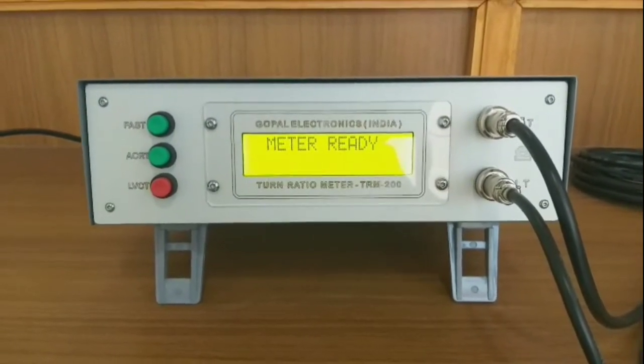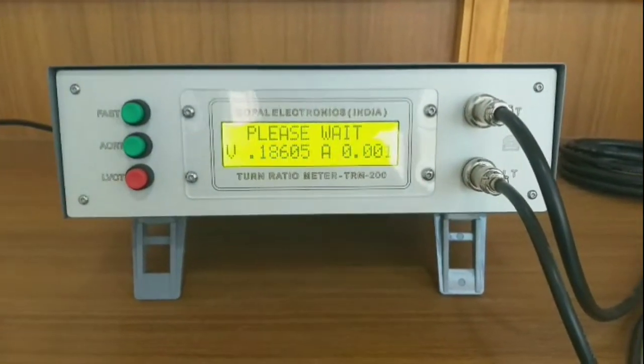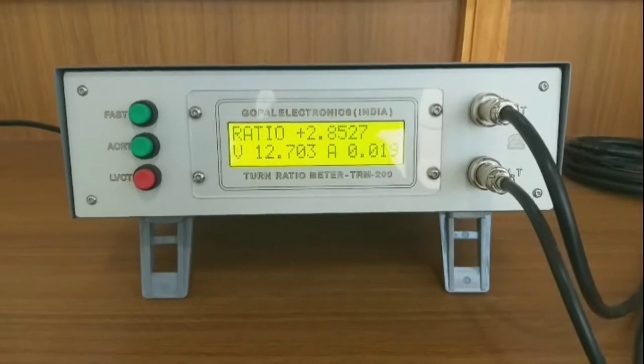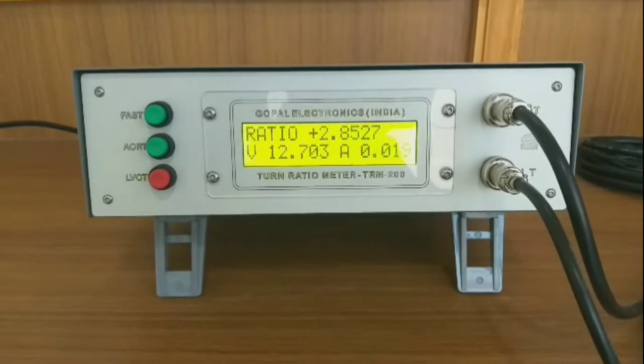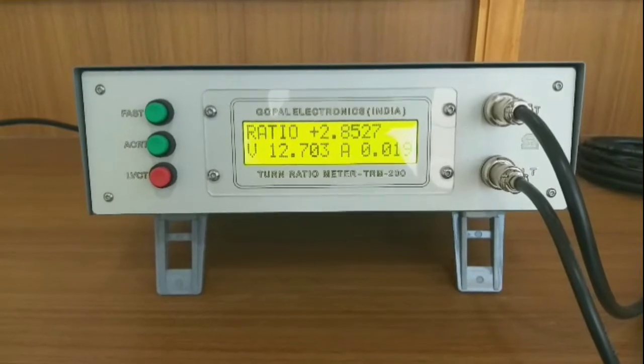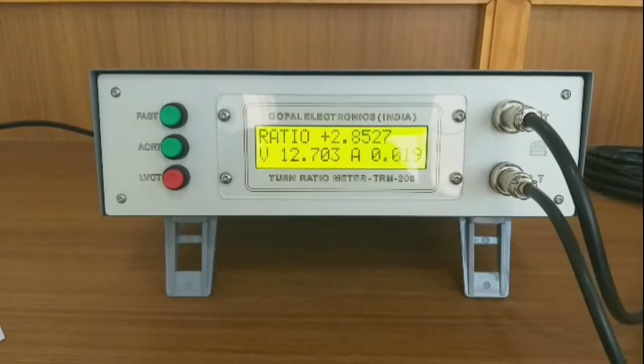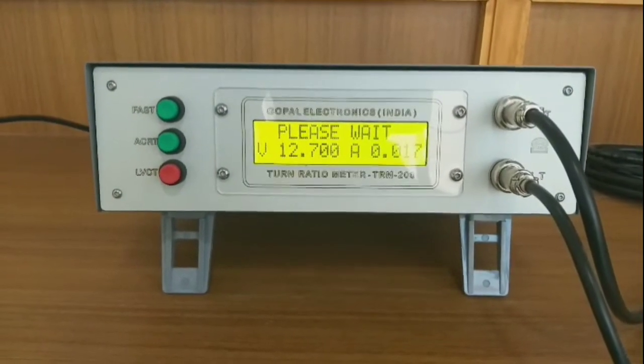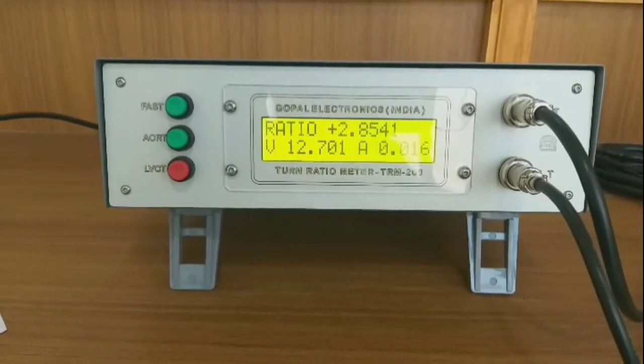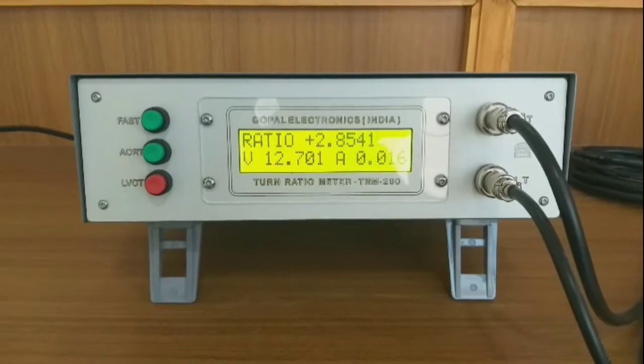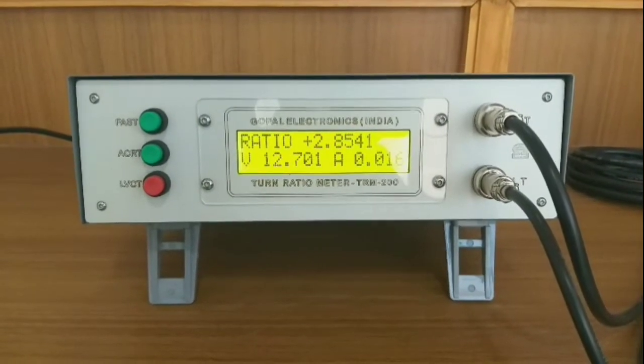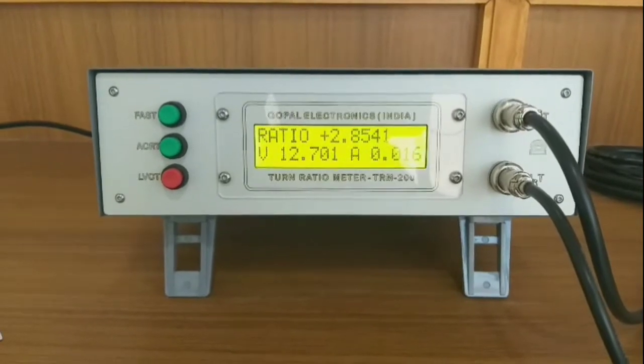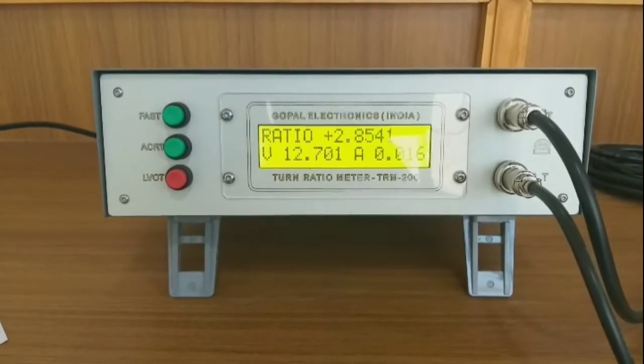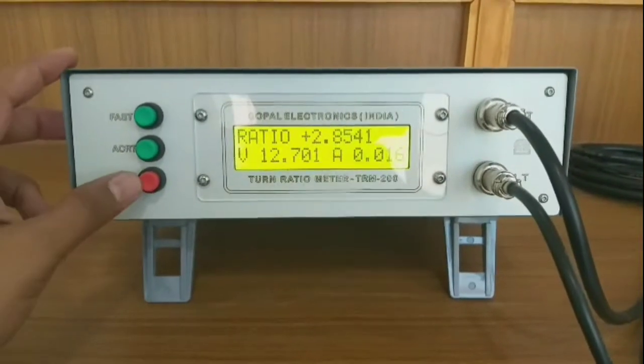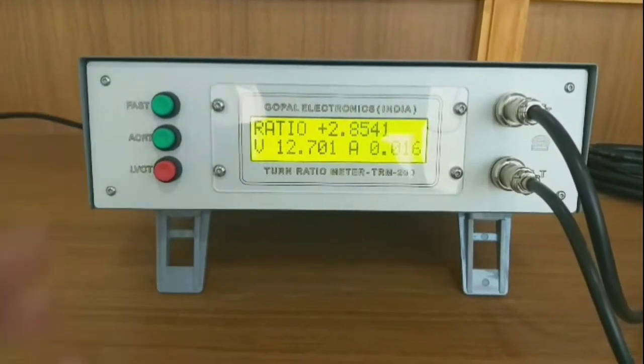To measure the turn ratio of R phase in fast mode, press the fast button. Turn ratio is 2.8527, voltage is 12.703 and current is 0.019 ampere. Now we will press the accurate button. In accurate mode, as I said, it applies all mathematical filters and then it gives the result. The ratio is 2.8541, voltage is 12.701 and current is 0.016. This equipment can measure ratio up to 1:1200, and LVCT is used to test short winding or to test CT, so I am not performing that.